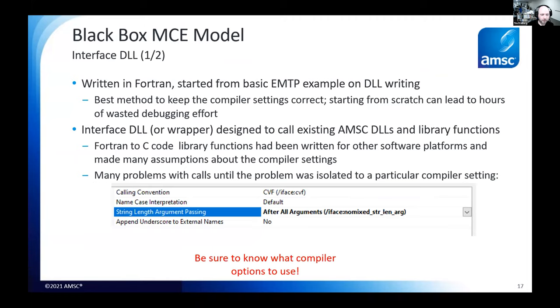The interface DLL we've written is in Fortran, as with most power simulation softwares, and we started from a basic EMTP example on DLL writing. If you choose to do this yourself, I really recommend you do the same thing — that's the easiest and best way to make sure all compiler settings are correct. If you try to do it from scratch and miss something, it can take hours to figure out what you missed. I know this because that's actually what I did. Henry at EMTP had told me not to do it that way and I did it anyway, so it took hours to find the mistake. It would have been easier to start from one of their example projects.